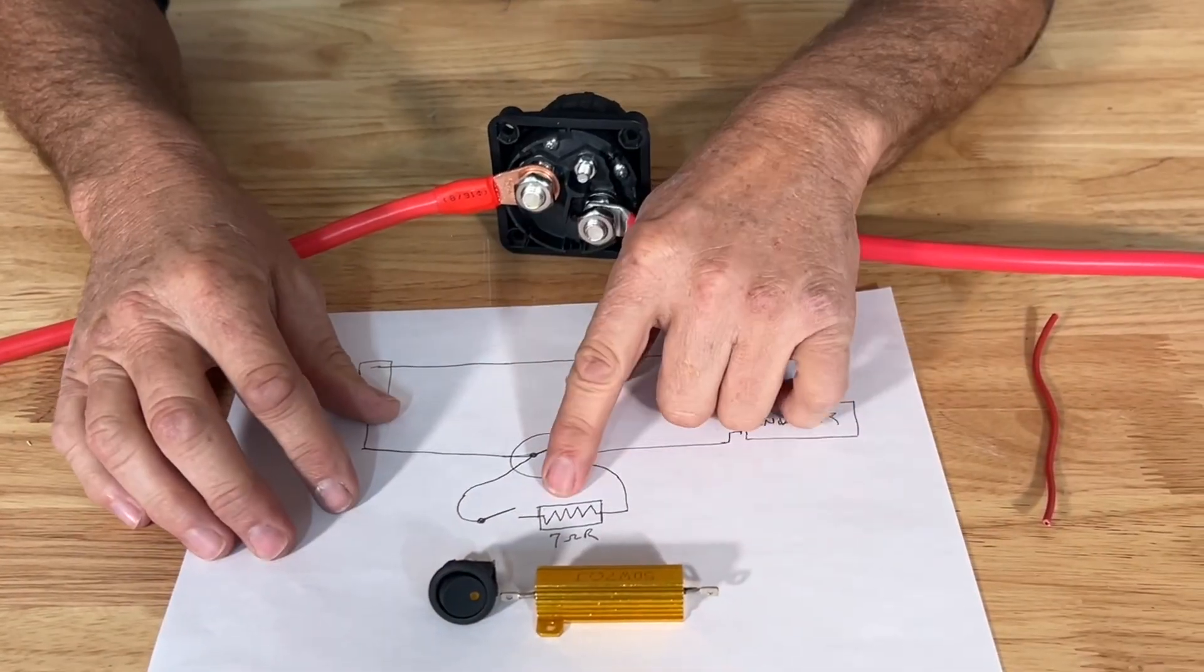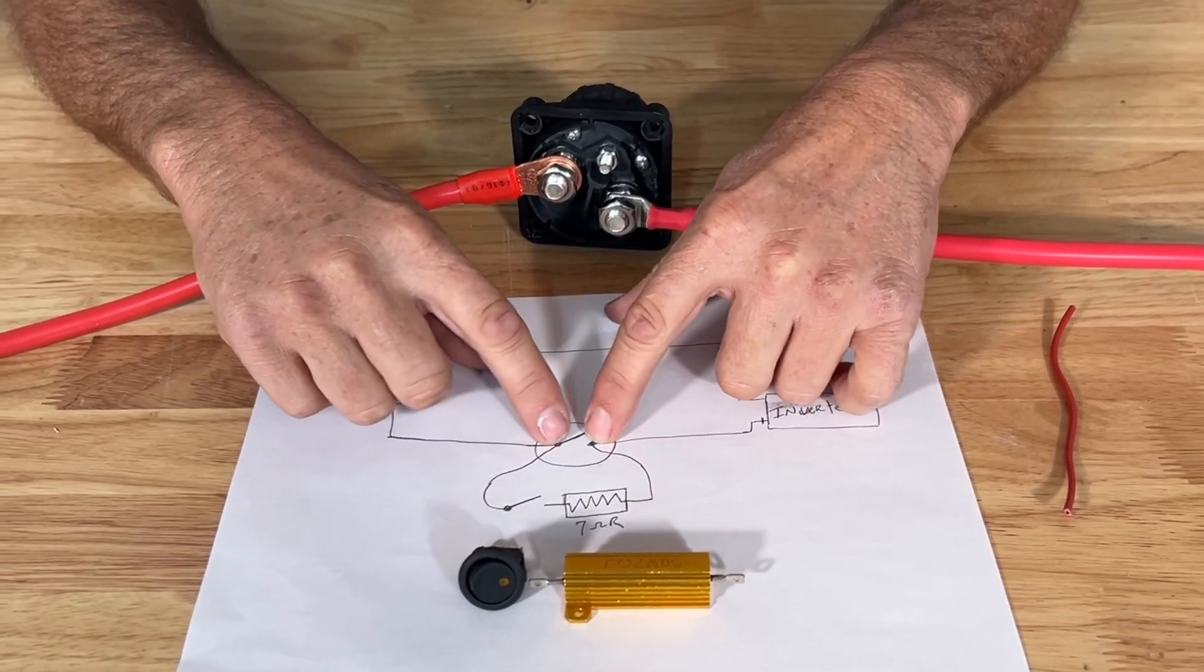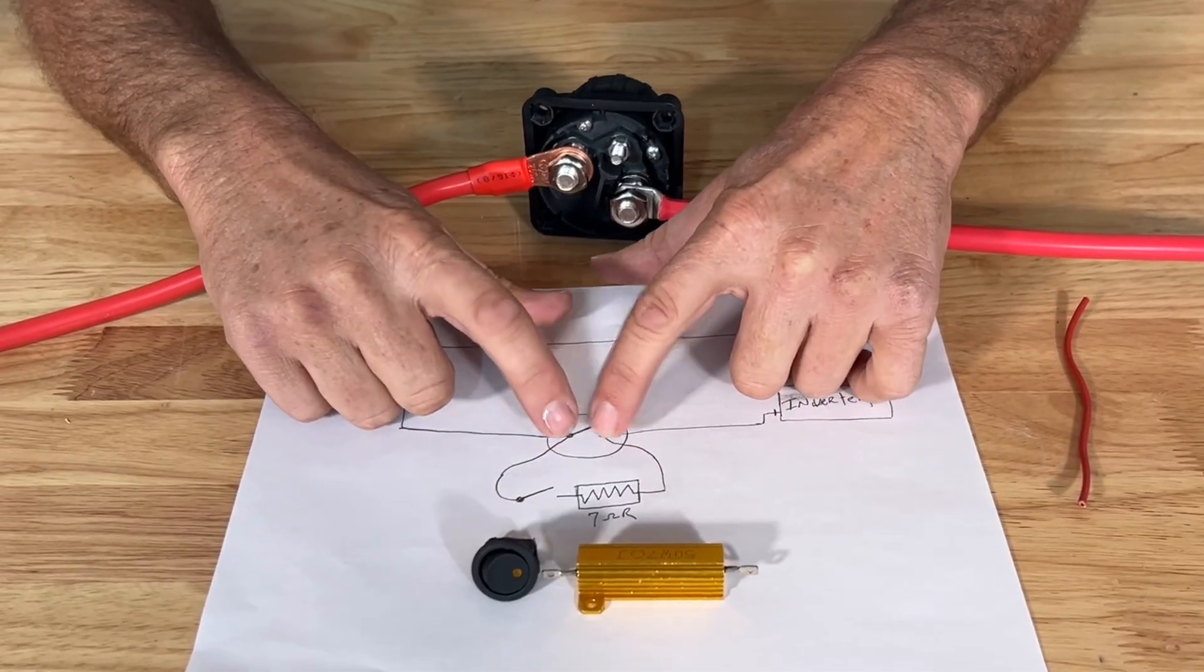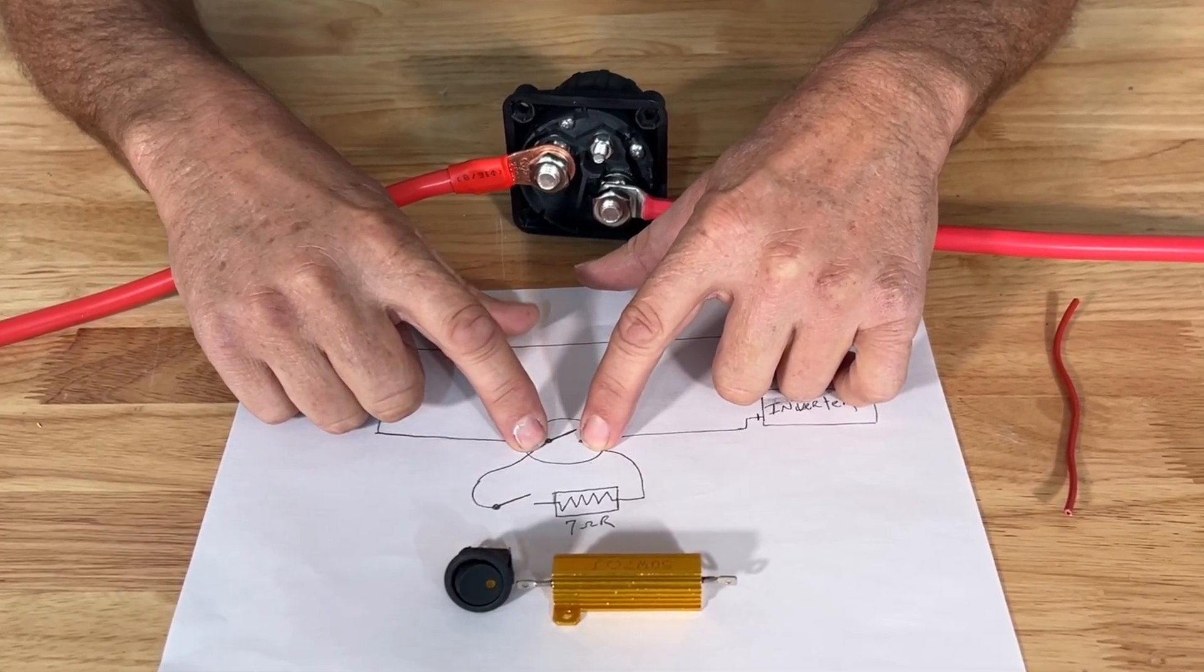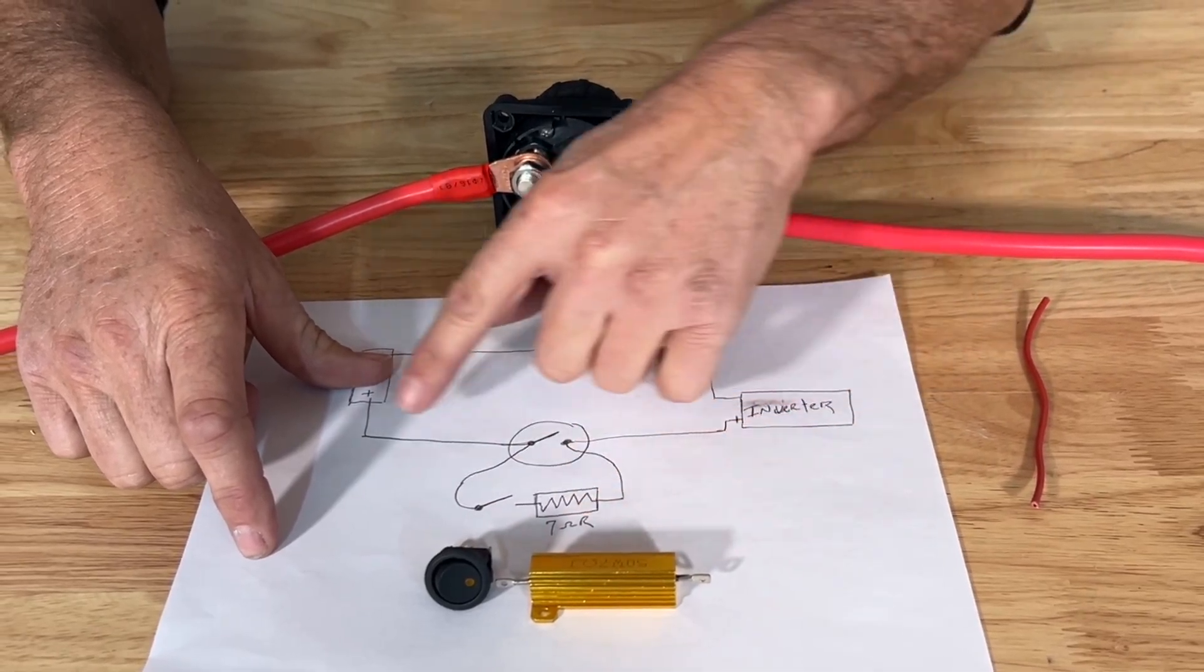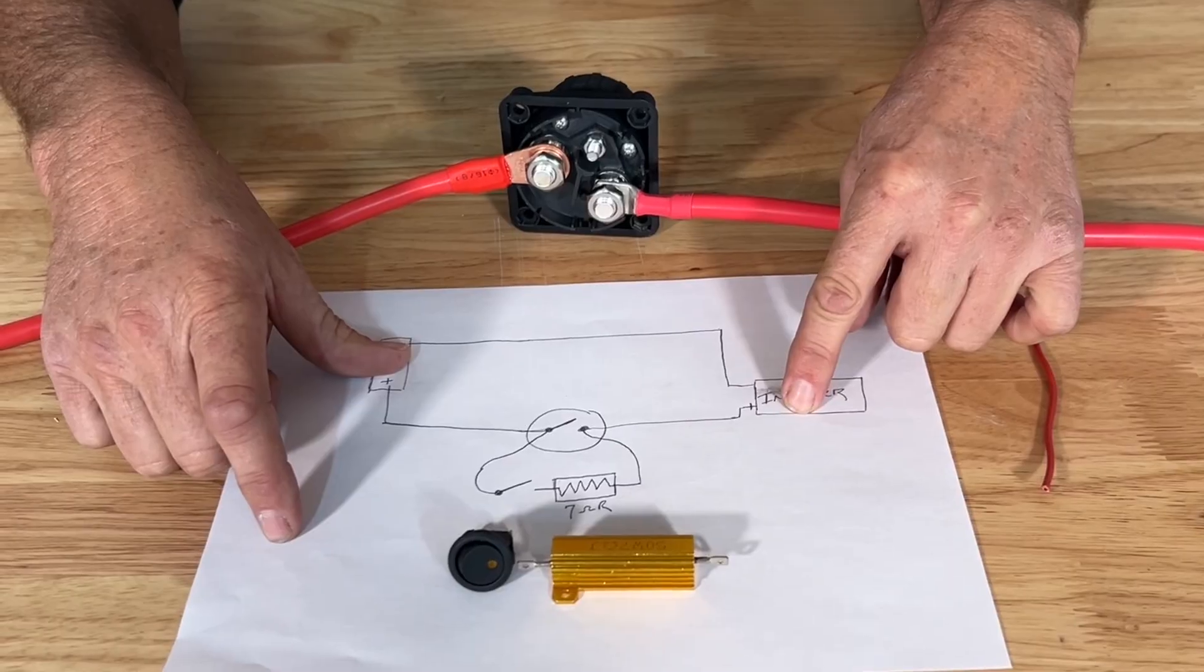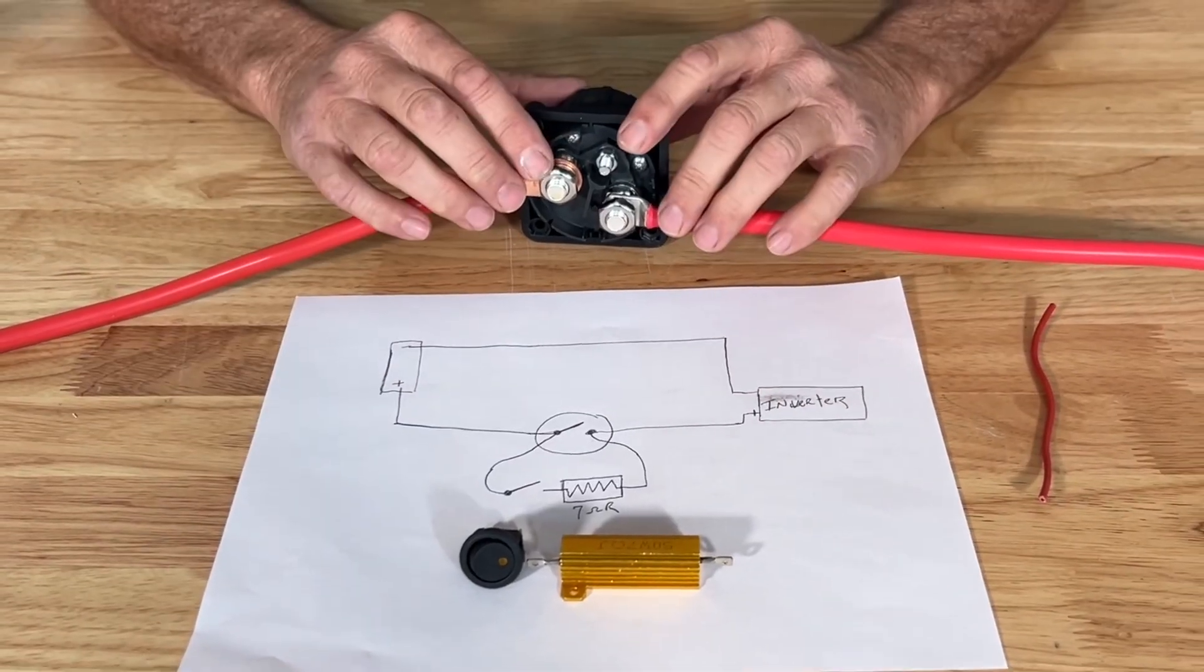So those are your 7 ohm resistor, your switch, and all you're doing is jumping this switch momentarily to prevent that inrush. So the power is going to come in, it's going to pre-charge the inverter, once that's done we can turn the switch on.